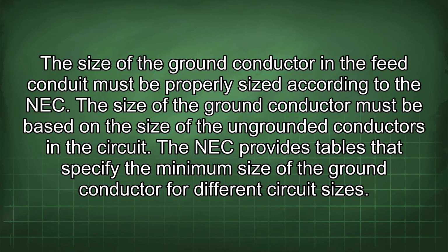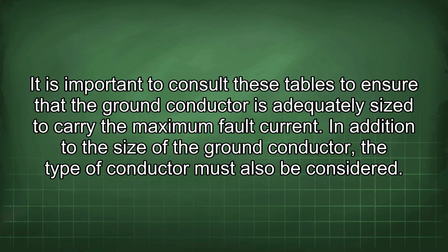The size of the ground conductor in the feed conduit must be properly sized according to the NEC. The size of the ground conductor must be based on the size of the ungrounded conductors in the circuit. The NEC provides tables that specify the minimum size of the ground conductor for different circuit sizes. It is important to consult these tables to ensure that the ground conductor is adequately sized to carry the maximum fault current. In addition to the size of the ground conductor, the type of conductor must also be considered.